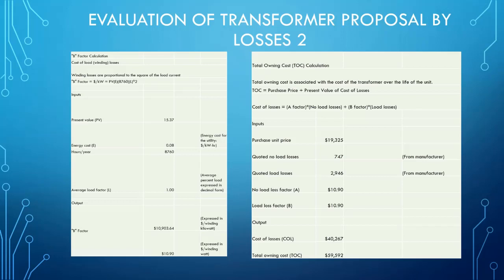Then to determine the total owning cost, they are going to, of course, add the no load losses to the load losses to get to their total losses. And at the end, they have a cost of losses. And they can add that to their first cost, and now they have a total owning cost of that transformer.